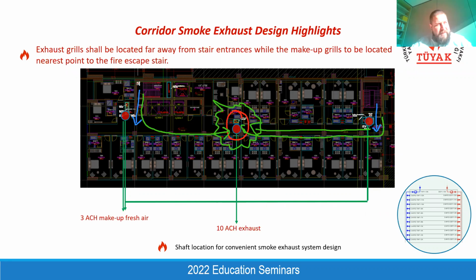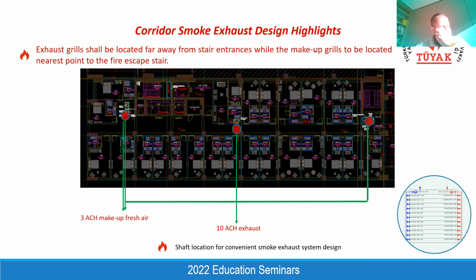This will give us two advantages. First of all, the people who are on this floor may easily find the staircase. They may see the staircase, they see their route, they see their path. And also when the fire brigade comes to the floor by the staircases, this one or this one, when they go out from the staircases, they have a clear area so that they can know where the fire is. If you have smoke accumulation just in the entrance of the staircases, neither the people on this floor can easily find the staircases, nor can the fire brigade coming to the floor easily distinguish the location of the fire. That's why the locations of the smoke exhaust shaft and the makeup air shafts are very important.